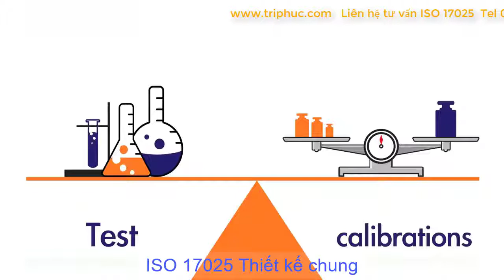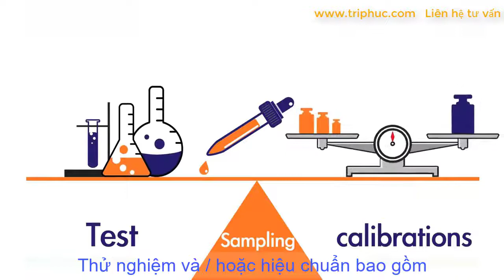Laboratories use ISO 17025 to implement a quality system aimed at improving their ability to consistently produce valid results. ISO 17025 specifies the general requirements for the competence to carry out tests and/or calibrations, including sampling. It covers testing and calibration performed using standard methods, non-standard methods, and laboratory-developed methods. It is applicable to all organizations performing tests and/or calibrations. These include, for example, first, second, and third-party laboratories, and laboratories where testing and/or calibration forms part of inspection and product certification.